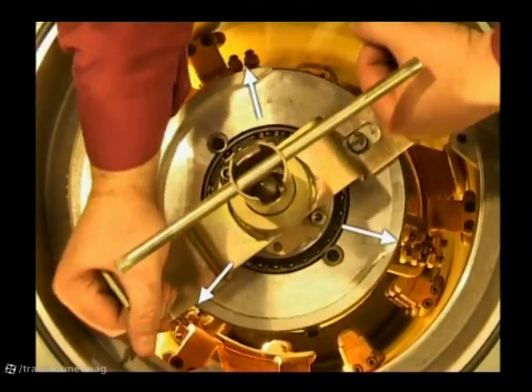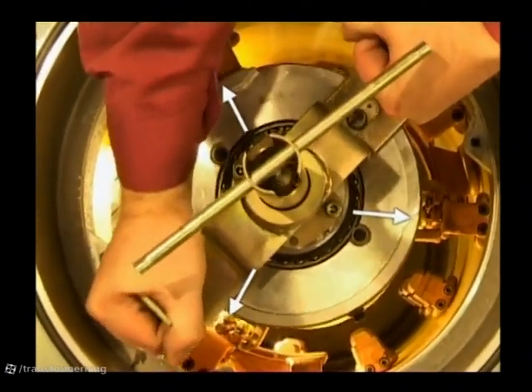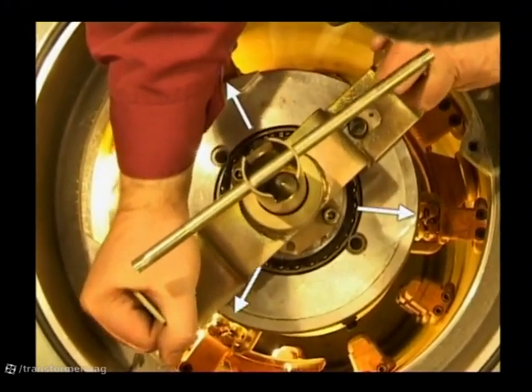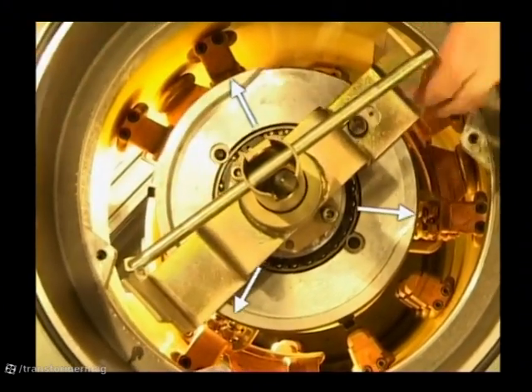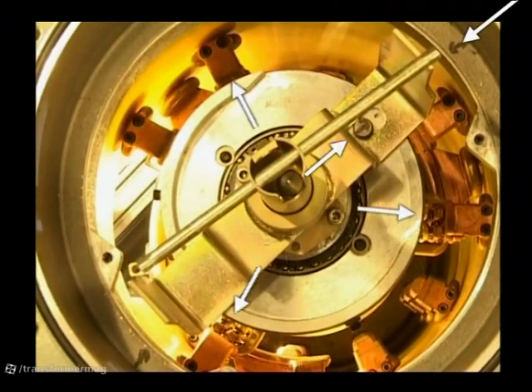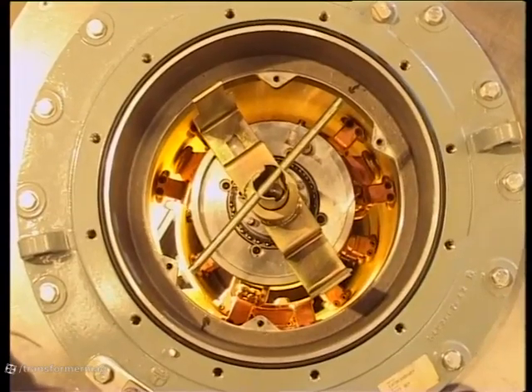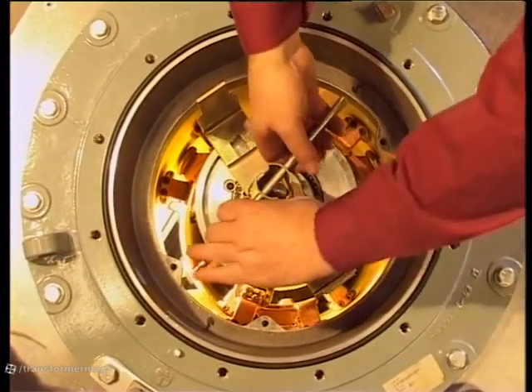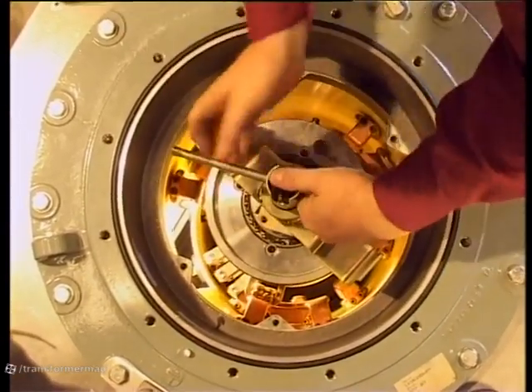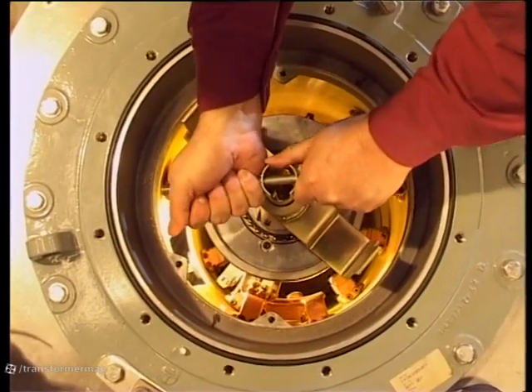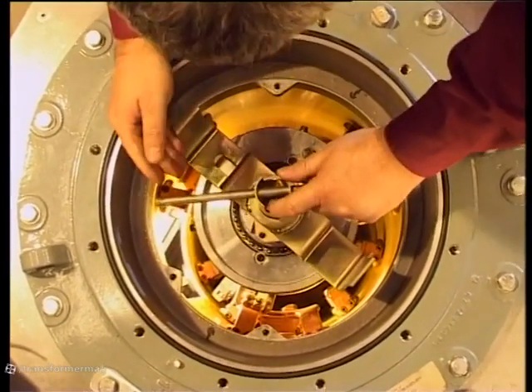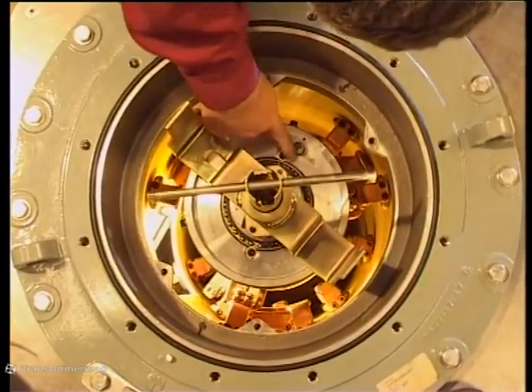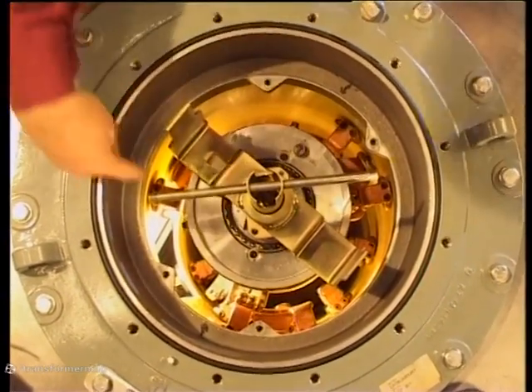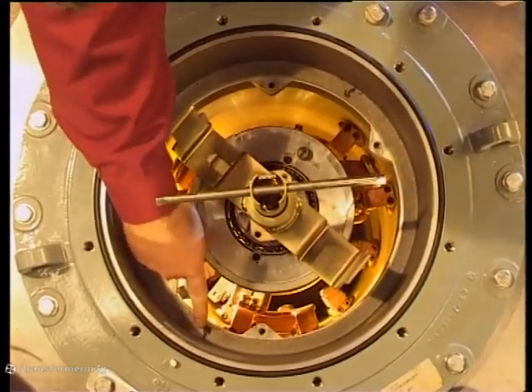Using the outer arms of the operating tool, turn the moving contacts to the position of their respective fixed contacts. Using the same tool, turn the selector switch so that its moving contacts meet the fixed contacts in the maintenance position. Check that the positions of the selector switch and the changeover selector are the same as those you marked before removal.